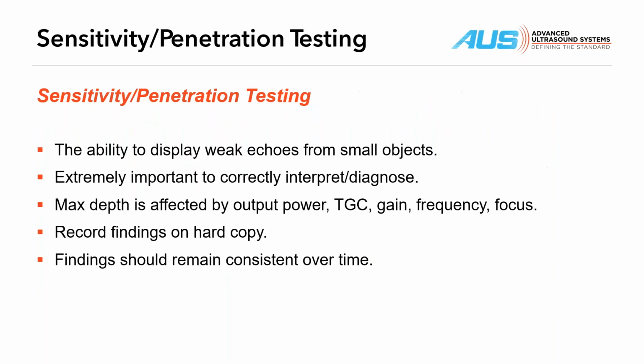So, okay, system sensitivity or penetration testing, the ability to display weak echoes from small objects. It's extremely important to correctly interpret and diagnose. Oftentimes, many people use the wrong objects on the phantom, and I'm going to point those out on the next slide. We'll go back and forth so you get a good understanding. Max depth is affected by output power, time gain compensation, which is your TGC sliders on the control panel, gain, frequency, and focus. Make sure you're setting these consistently throughout the PM.